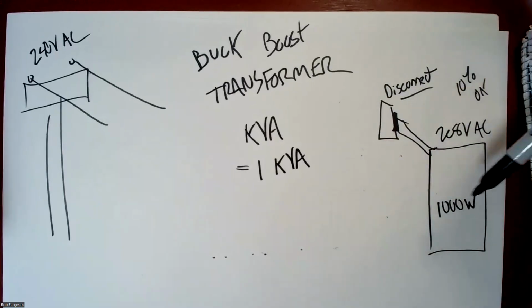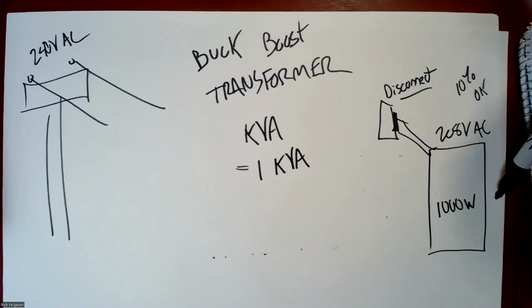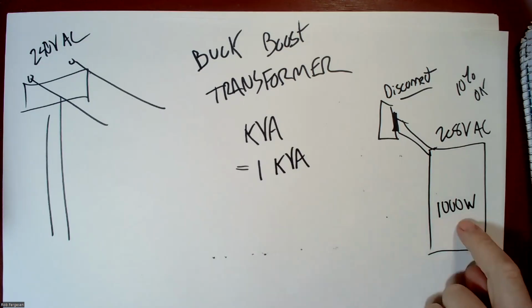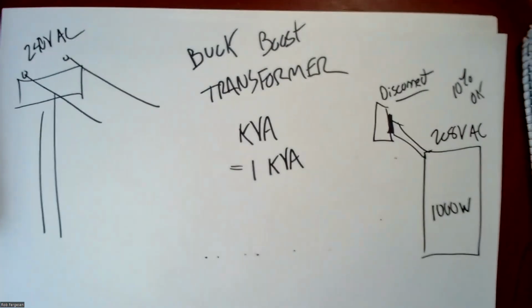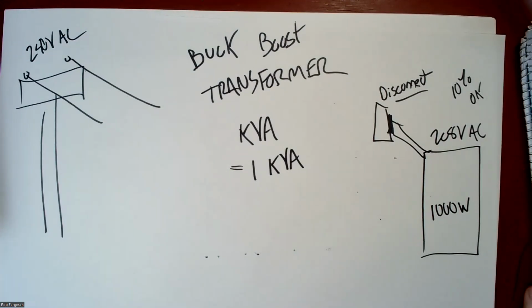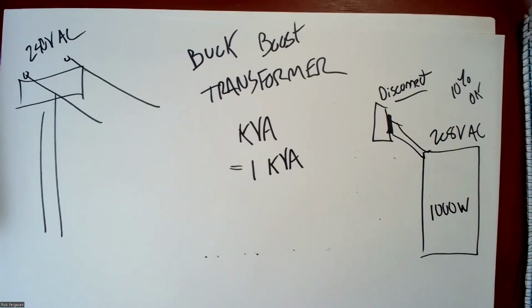Okay. If I had three-phase power, I would actually multiply this by the three-phase power factor, which is 1.73, I think. And so I would need to do that multiplication to give the size of the transformer. So my transformer would have to be slightly bigger. But since I'm using single-phase power, volt amps is equal to your watts, essentially. So I need to go find a 1 kVA transformer. And I need to find a good wiring diagram to show me how to use that 1 kVA transformer.